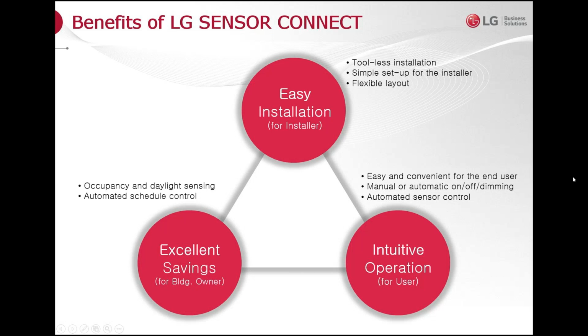The savings come not only from our high efficacy, so we have one of the highest lumen per watt efficacies, but also if you purchase our lights with controls, so if you ordered one of our Sensor Connect lights, which comes with a sensor in it, or you order a light with a dongle, as soon as you power it on, the controls automatically trim the high end down to 80%. So that's the default high-end trim. There's a lot of rebate programs out there that require 80% as one of the requirements to be eligible. So just having this light plugged in with a dongle or a sensor already has an 80% high-end trim, and these sensors already come with motion and daylight activated. You can further the savings by grouping them together with the app and adding a switch which can also dim and schedule it. So lots of ways you can squeeze out savings out of an already low wattage, high performance product.